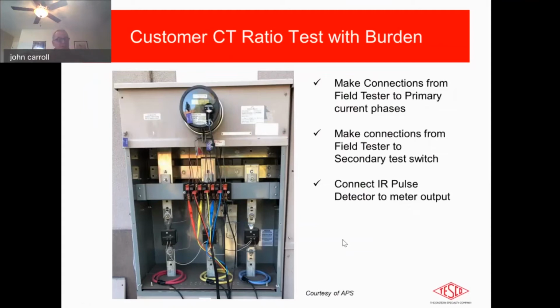So let's move on a little bit to doing our CT ratio test. What we have now is a CT ratio test with burden. This is a typical setup. In this particular type of condition, we have the meter in the separated column at the top of this panel, and then a separate panel which opens up the primary cabinet, where we can see our 3 CTs in there. There's our bus bars, there's A, B, and C. There's our test switch, and there's the wraparound flexible probes where we pick up the current flowing through that CT.